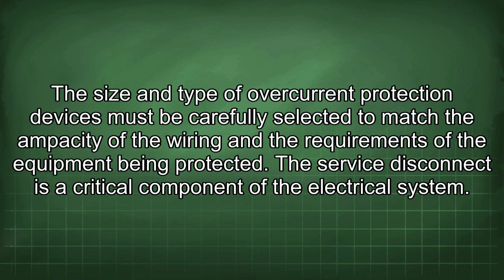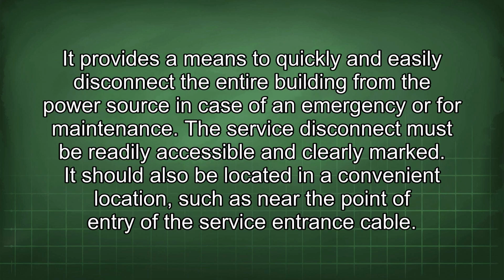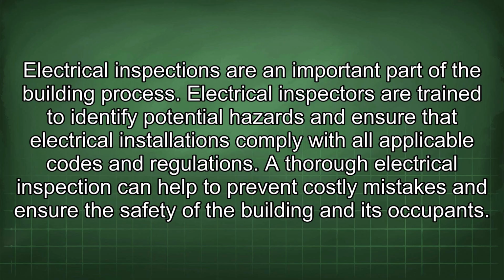The service disconnect is a critical component of the electrical system. It provides a means to quickly and easily disconnect the entire building from the power source in case of an emergency or for maintenance. The service disconnect must be readily accessible and clearly marked. It should also be located in a convenient location, such as near the point of entry of the service entrance cable. Electrical inspections are an important part of the building process. Electrical inspectors are trained to identify potential hazards and ensure that electrical installations comply with all applicable codes and regulations. A thorough electrical inspection can help to prevent costly mistakes and ensure the safety of the building and its occupants.